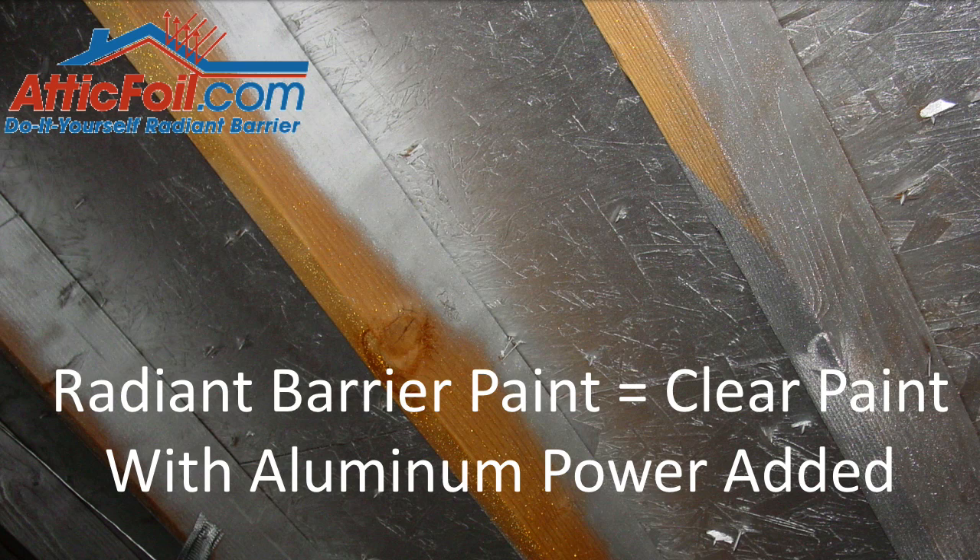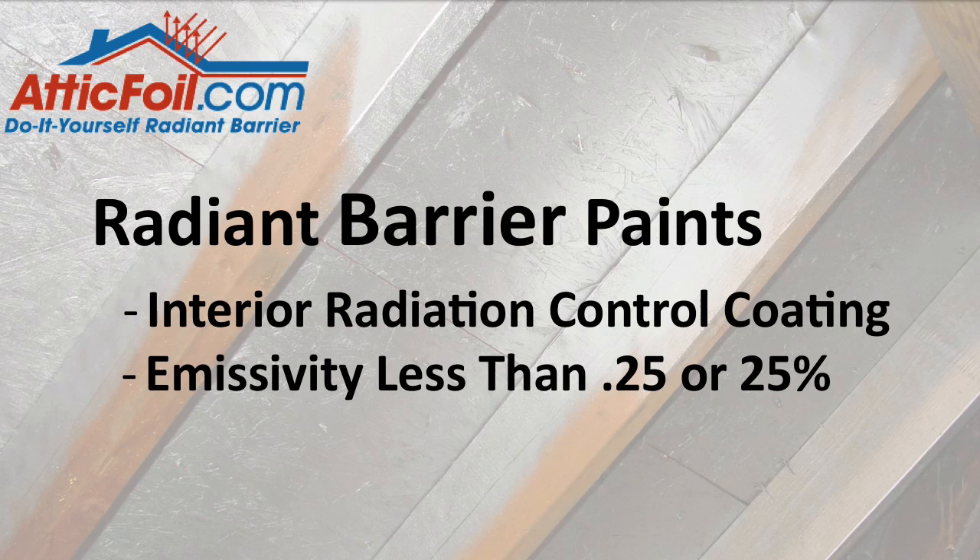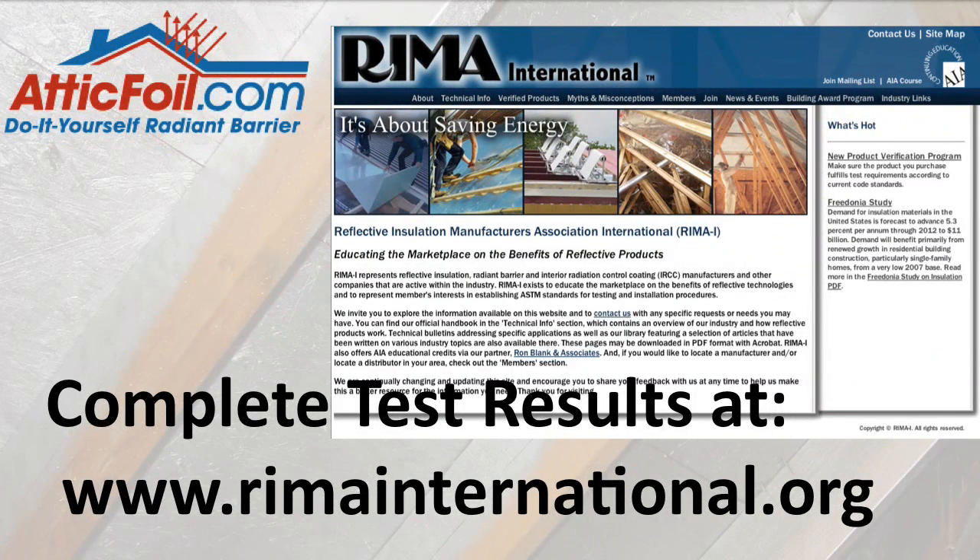Here are some differences between Radiant Barrier paint and Radiant Barrier foil. First, Radiant Barrier paint is technically not even a Radiant Barrier. A Radiant Barrier by definition is a product that either reflects over 90% or has an emissivity quality of less than 10% — meaning it emits less than 10% of the heat. Radiant Barrier paints are technically called Interior Radiation Control Coatings, or IRCCs, since they did not achieve the 10% emittance standard. In fact, testing done by RIMA International shows only 4 out of 18 products even meet the definition of an IRCC, which requires less than 25% emittance. Some companies rebrand these products with their own labels, making it extra difficult to find any technical information on them.